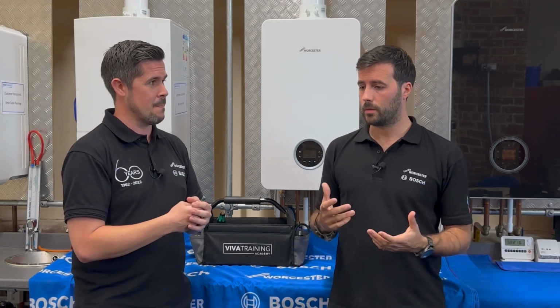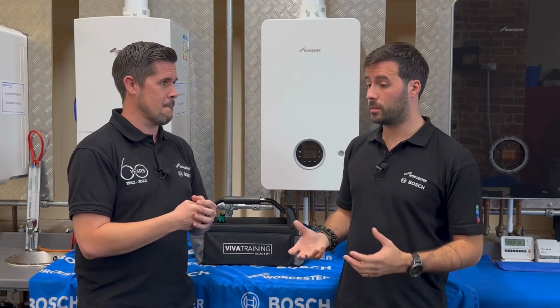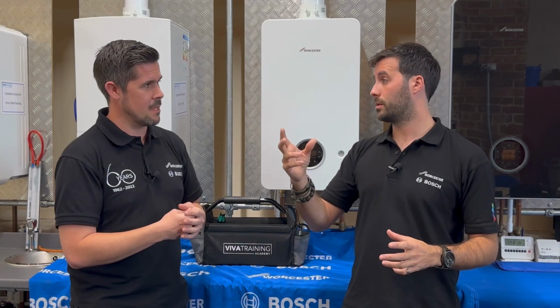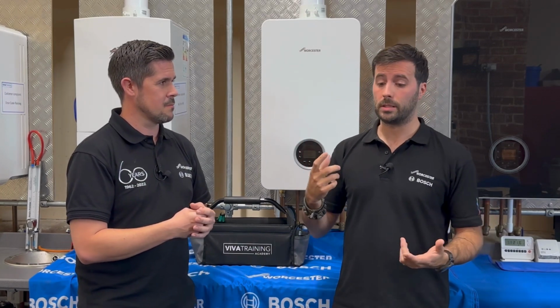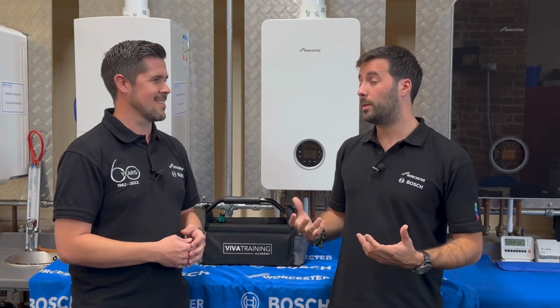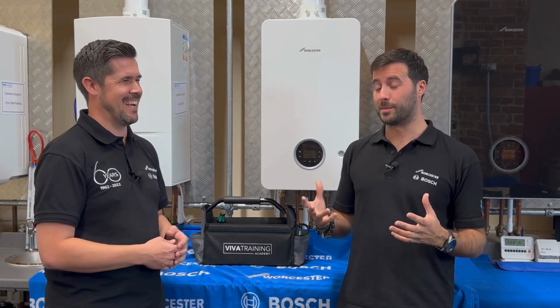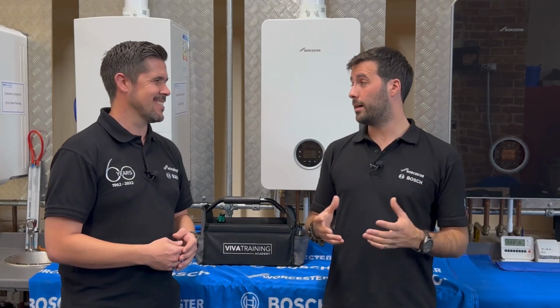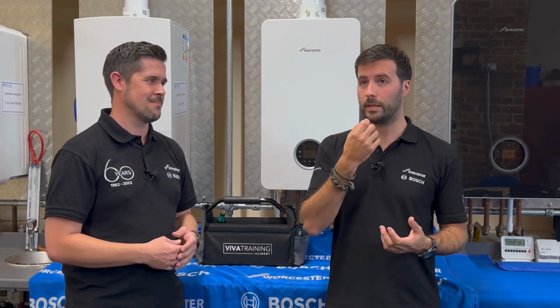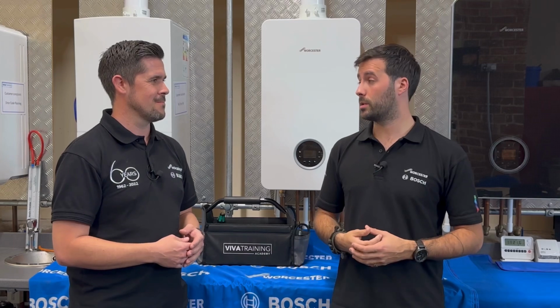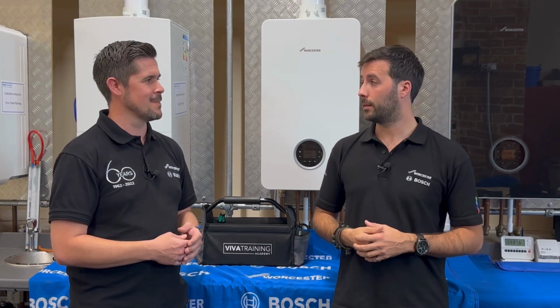Yeah, exactly. So on a modern condensing system, the difference we're looking for is 20 degrees. But to achieve that, you need to balance the system correctly. The system needs to be installed and spec'd for it. How many people just throw a boiler on and don't balance the system? So it's really important to do that, and it's not exactly hard either. No. So there's no reason why not, especially when you are talking to customers and all they are thinking about at the minute is how can I save money? Money. Yeah. Brilliant.